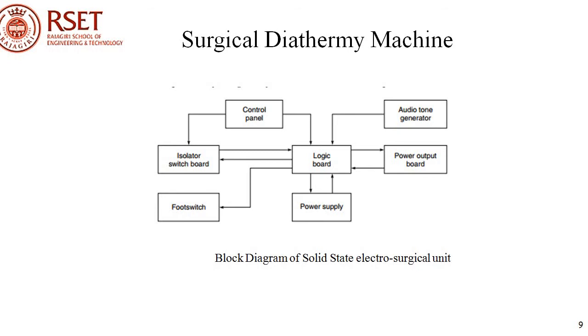A 250 kHz signal provides a split phase signal to drive the output stages on the power output circuit. A 15 kHz gating signal produces the repetition rate for the 3 cycles of 250 kHz signal, which make up the coagulating output. And the 250 kHz signal used for cutting is given to the power output stage, where it controls the push-pull parallel power transistor output stage.